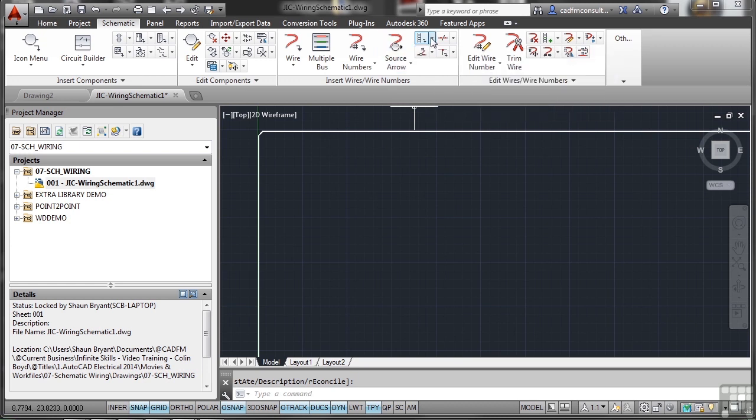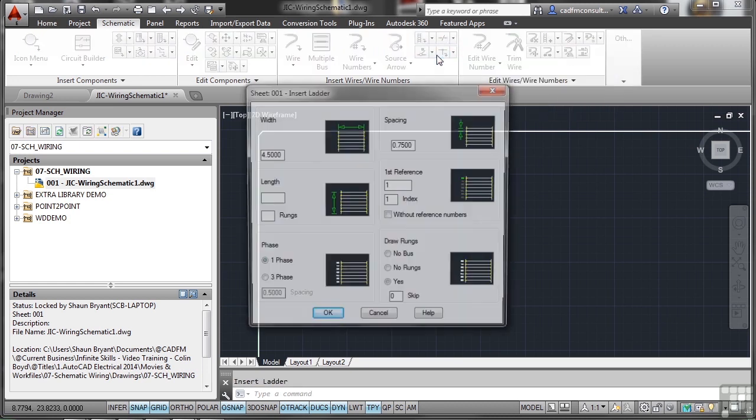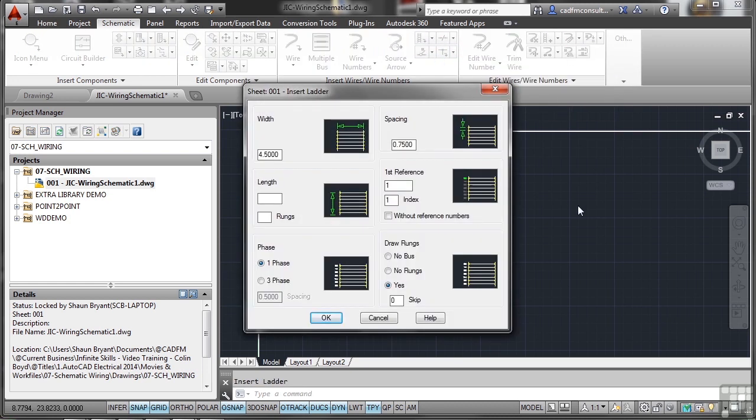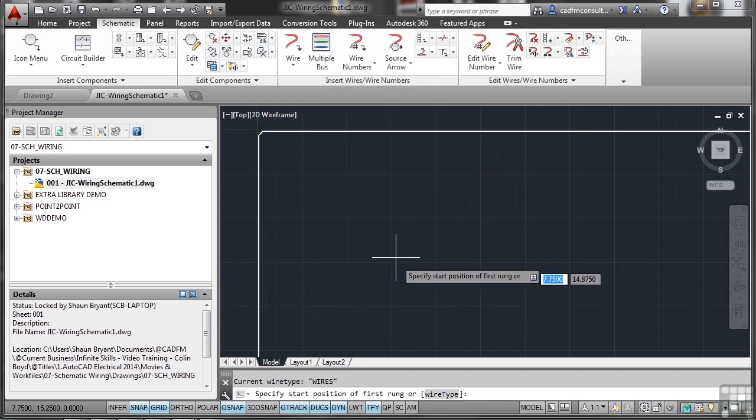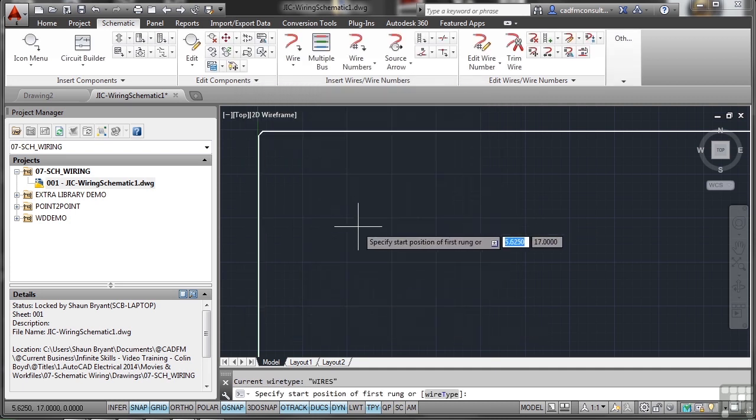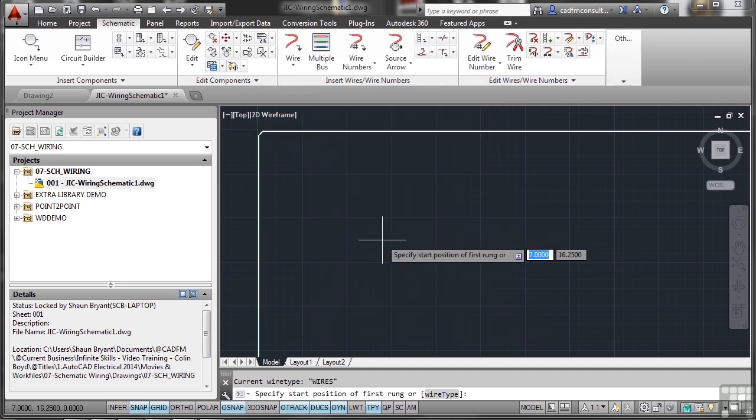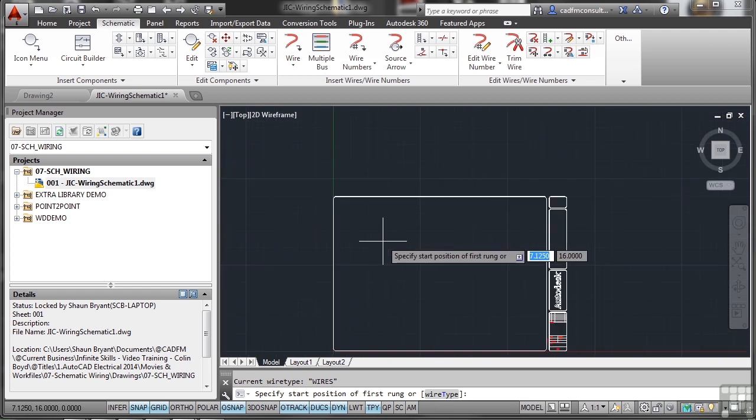I'm going to insert some wires and wire numbering by using the ladder tool. Width at the moment is 4.5 inches with a spacing of three quarters of an inch. I'm going to change that to 15 inches with a spacing of one inch for each one, and I want 15 rungs. I want it to be one phase, and yes I do want the rungs drawn in between the buses on the ladder.